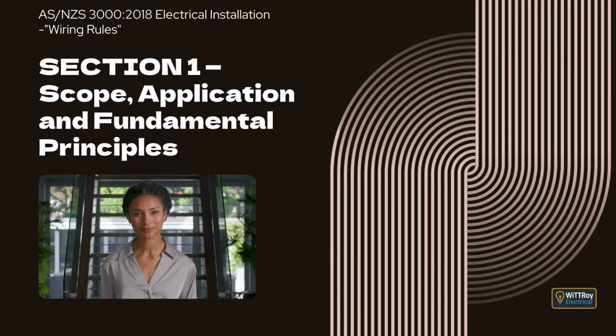Clause 1.4.99 is protective earth neutral, also called PEN. This is where the neutral and protective earth functions are combined in one single conductor. Clause 1.4.100 is protective earthing conductor. This is an earthing conductor, other than the main earthing conductor, that is intended to carry earth fault currents or to connect parts of the installation to the earthing system so they are safely earthed.